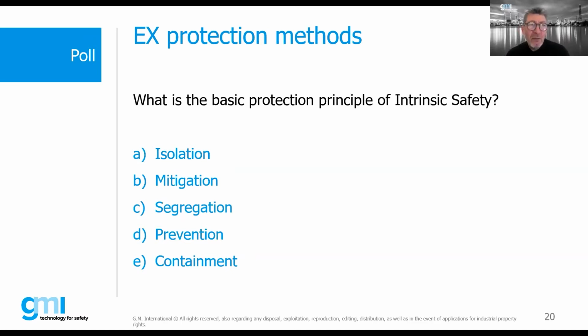So, is increased safety a prevention concept or not? Yeah, it is actually a prevention concept. How about non-incendive also? Non-incendive is an interesting one, yes, it is also a preventive concept. Non-incendive is actually a protection concept recognized here in the United States, but it's not one of the protection concepts recognized internationally, so we don't talk about non-incendive in the IEC world. However, in the US, we say these devices are incapable, by their design, of igniting a flammable gas atmosphere under normal operating conditions.